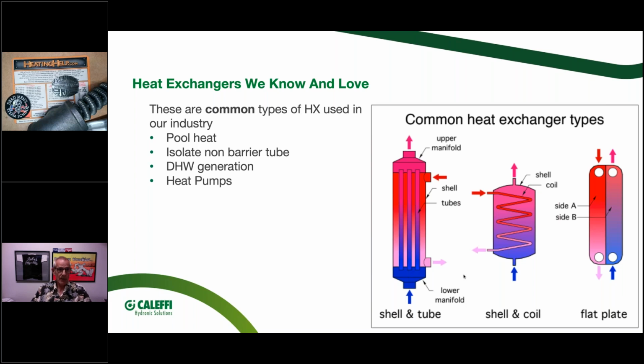That's what I'll go through tonight: why would I choose a shell and tube as opposed to a flat plate? Places you'll see these used commonly: snow melt systems sometimes, if you're trying to isolate the glycol from a boiler; heat pumps, a lot of times you'll have a little desuperheater on the heat pump; and domestic hot water generation, which is getting to be a really big application. As we see more of these combi ModCon boilers—because the ModCon boilers just have a little plate heat exchanger inside them—when you turn on a faucet somewhere, a flow switch triggers either a relay, a zone valve, or a second pump, and it generates instant domestic hot water from your boiler.